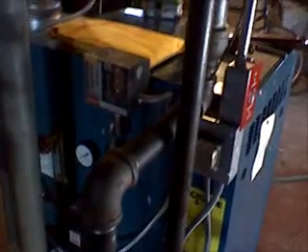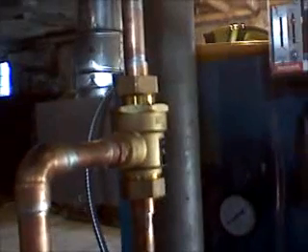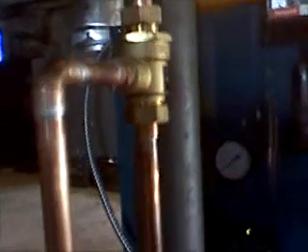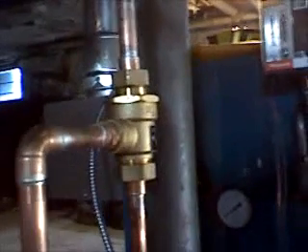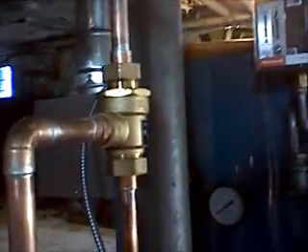Again, all boilers should have a backflow preventer, and this is ours, so that way we don't suck back the boiler water. Years ago, you only needed a backflow preventer if it had an automatic feeder, but I put them in anyway. Here's our pressure gauge, where again, you don't want pressure on steam. And there's our glass gauge to monitor the water level.